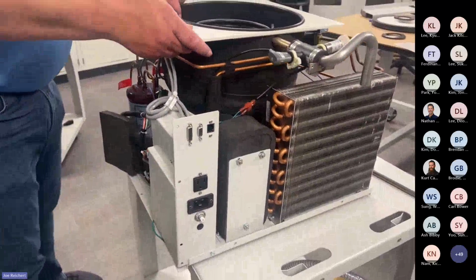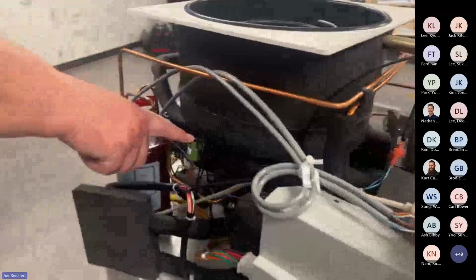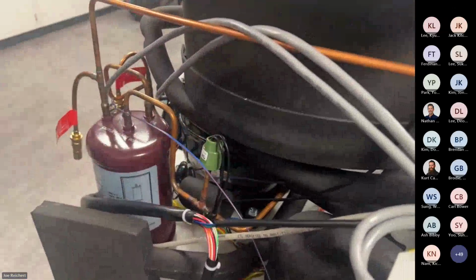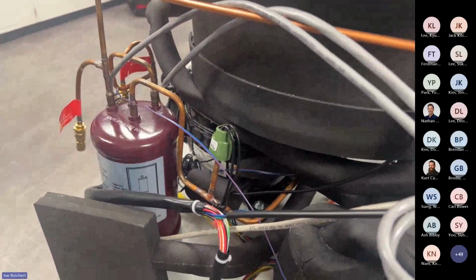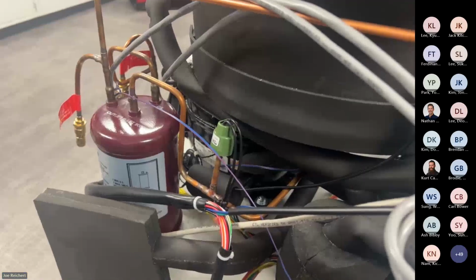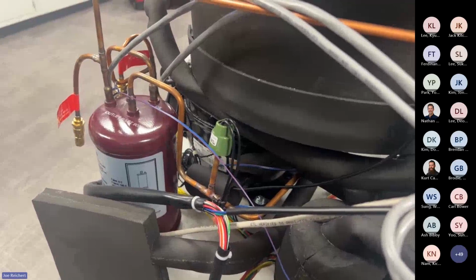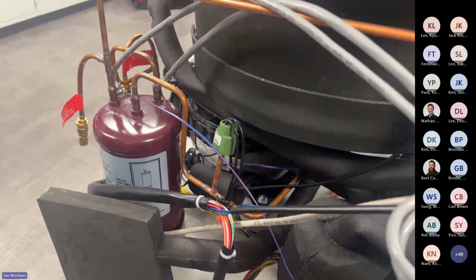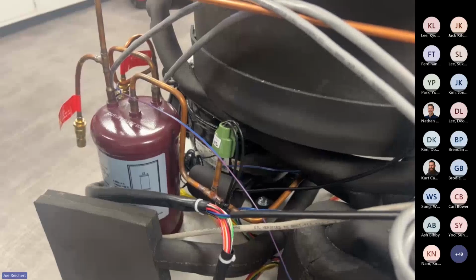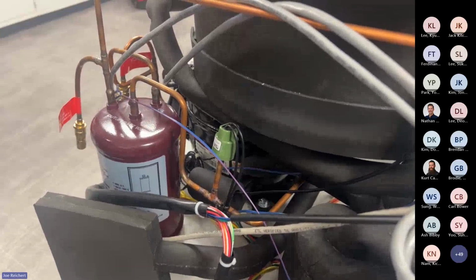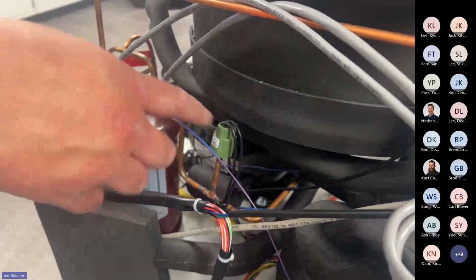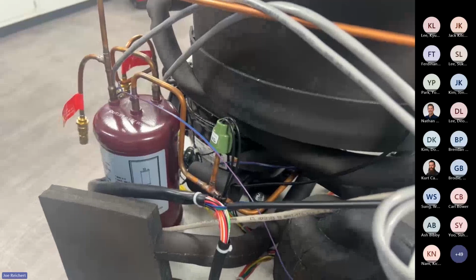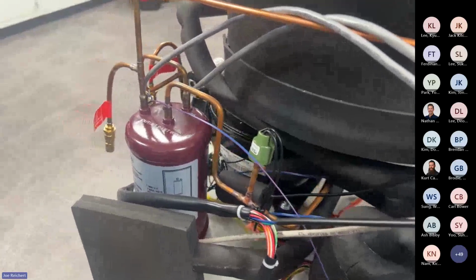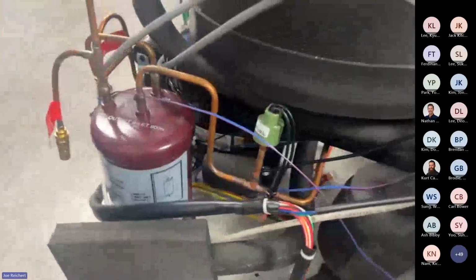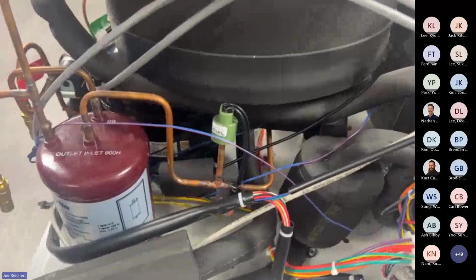This is also a piece. We have the pressure switch that is there for between your first stage and second stage. If the first compressor does not cool the gas enough of the second stage, then the pressure will be too high within that second stage. So this switch will shut the second system down if the pressure is too high. And that's about it on our benchtop models.